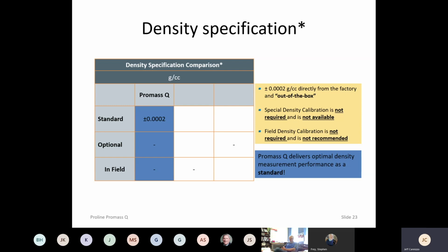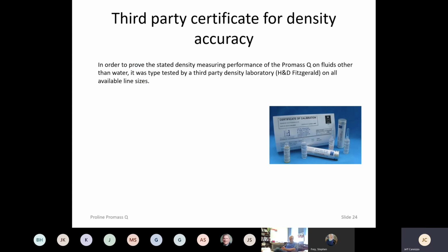But the Promass Q is a guaranteed 0.0002 field accuracy. So you don't have to do a field density calibration, and it's not even recommended. And we don't even offer a special density calibration for this meter. And we don't just say it, we've actually proved it.